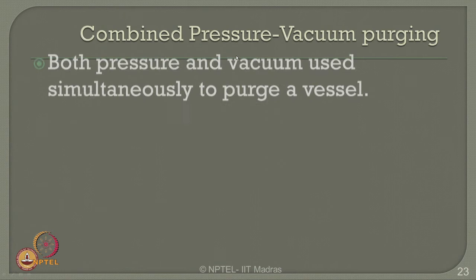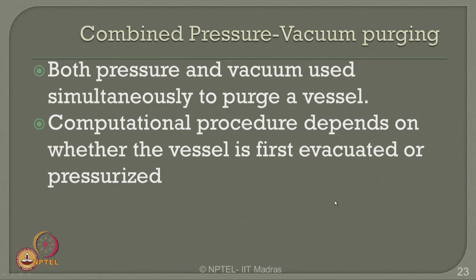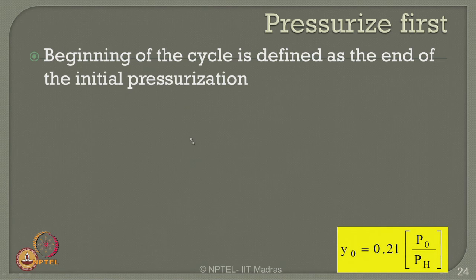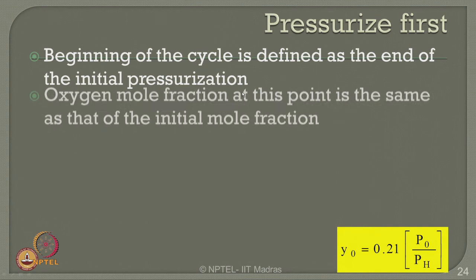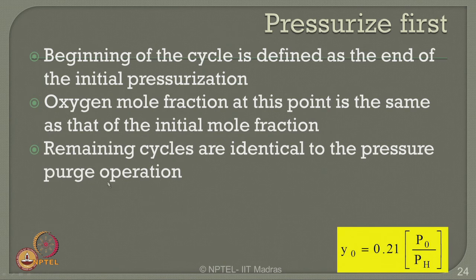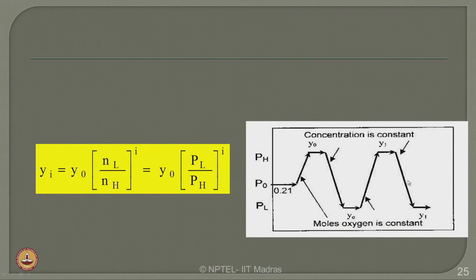The oxidant concentration for the i-th cycle, Y_i, is given by the ratio of P_L to P_H for I cycles multiplied by the initial value Y naught. One can also do combined pressure and vacuum purging. Both pressure and vacuum purging are used simultaneously to purge a vessel. The purging procedure depends on whether the vessel is first evacuated or pressurized. If pressurizing first, the beginning of the cycle is defined as the end of the initial pressurization, and Y naught is 0.21 times oxygen with P0 and P_H known.